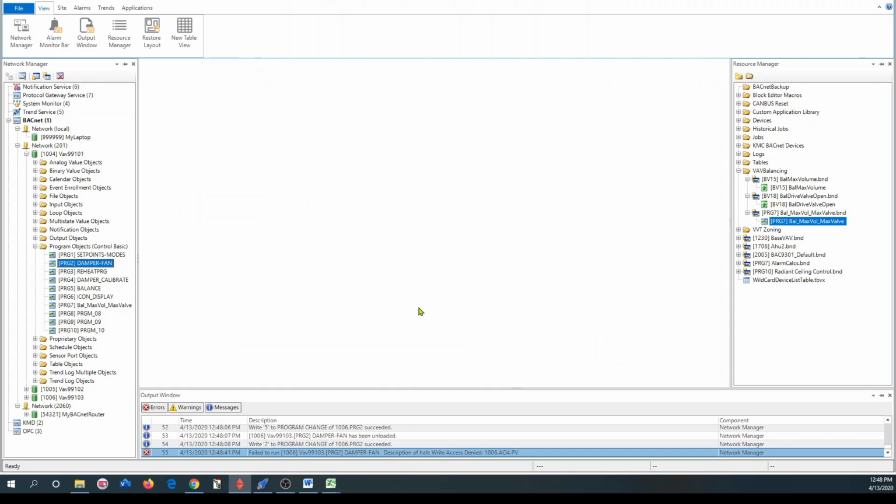One of the things that KMC has corrected in more recent releases was the fact that it would sometimes not always send it to a certain controller. Maybe it would just quit if it sent it to 10 of 20 controllers and then it couldn't do something, so it said, screw it, I give up. Or it would leave the controllers in idle mode instead of running, and you wouldn't know.